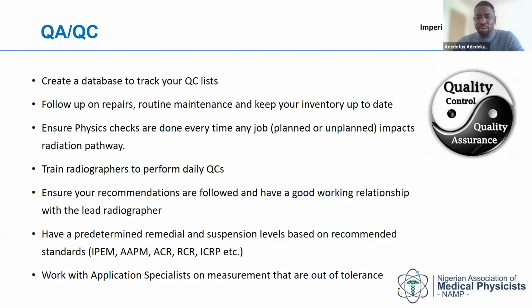You just tell them, and then when anything they measure, the essence of the radiographer's QC, the essence of QC in the first place, is that you want to discover any fault, any malfunction before it becomes clinically noticeable. All right. So when a radiographer has done maybe the AEC chamber test and they discover that one of the AECs is not giving the right time or dose, then they reach out to physics, and then you go there and you intervene. And then you try and troubleshoot to see what the problem is.